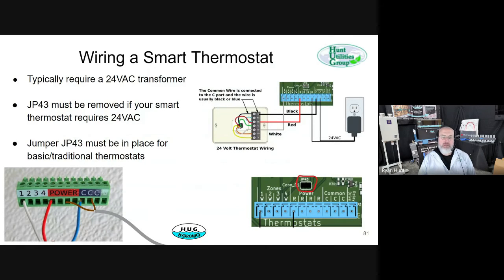Okay, here's a diagram of what that smart thermostat looks like. They take the 3 wires, but they require 24 volts, so we have an outside 24 volt power supply. That connects to the R and C terminals. And you pull that jumper because our board runs on 12 volts, and pulling that makes sure that the 24 volt doesn't backfeed into the board. Backfeeding won't break the board, but it won't work quite right either.